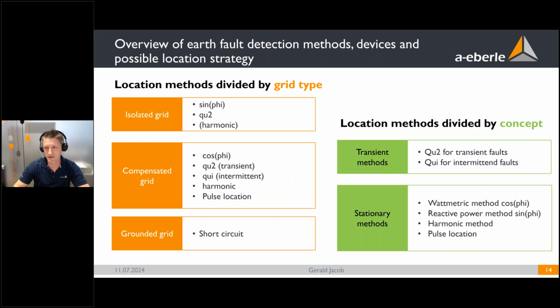What are these methods? We see on the next page you can divide these location methods by grid type, so which methods you can use in which type of grid. Mainly there are 3 to 4 different kinds of grids: isolated grid, compensated grid with suppression coils, and grounded grid. There's also low ohmic grounded grids, but there's always a question of how low ohmic these grids are grounded.